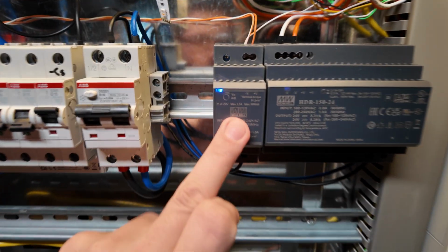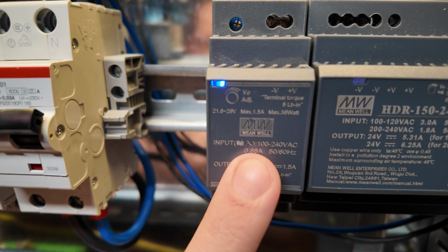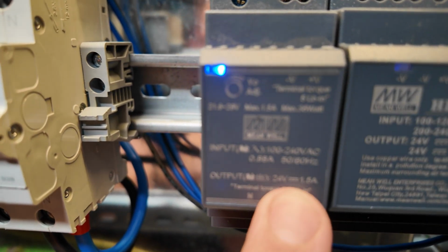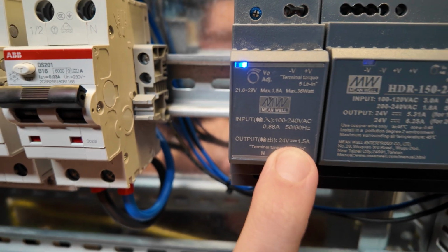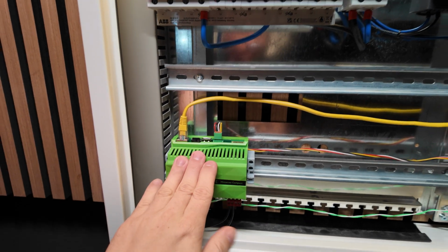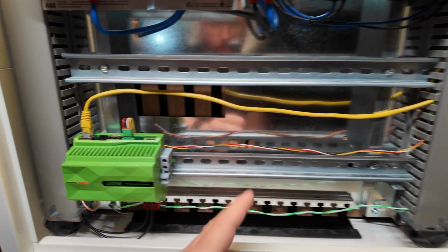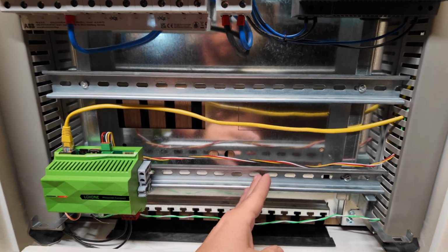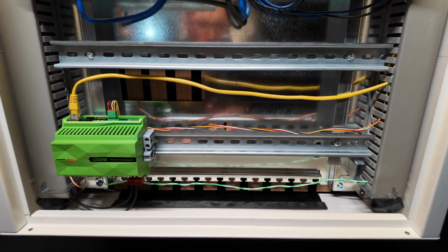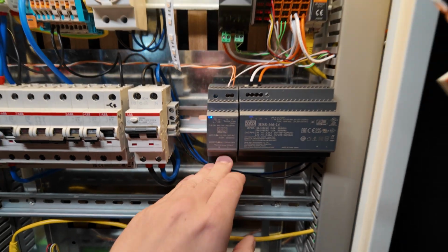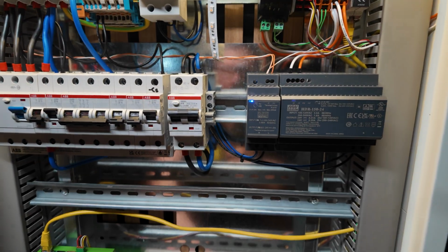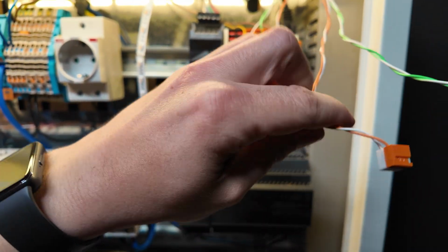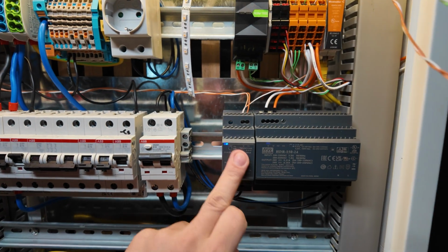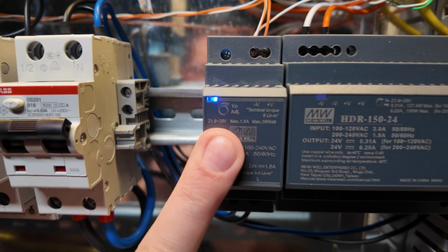And what I always do here as well is I use a dedicated, in this case 1.5 ampere, power supply only for the Miniserver and maybe its extensions, let's say relay extension, digital input extension, Air base extension, and so on. Not for the push buttons and everything else. Same story: if there is a short circuit on the push button side or whatever, then the Miniserver's power supply is not affected by it either.